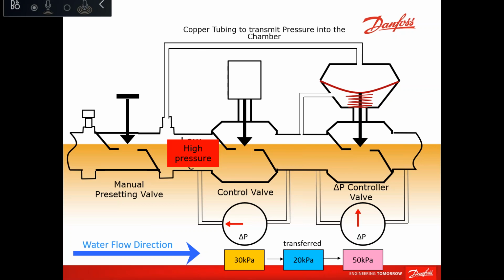So yes, it can still give you the minimum system set flow, even if the pumps are running at 100%. Okay. If we are replacing the two-way control valve with the PICV, is it enough to open the DRV to max setting, or do you recommend removing the DRV from the system? If you open the DRV fully and the pressure drop across it is very low, then keep it. But if you put the DRV at full and the pressure drop is still high, that might affect your available system head, then remove it.